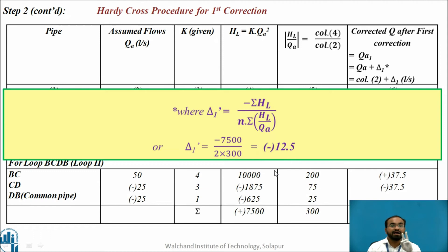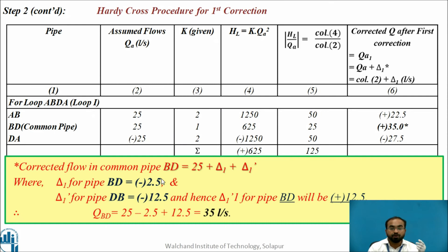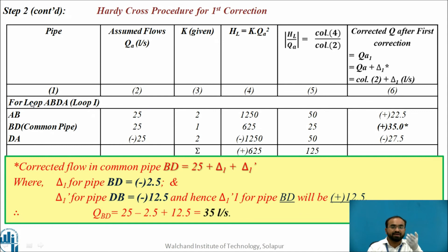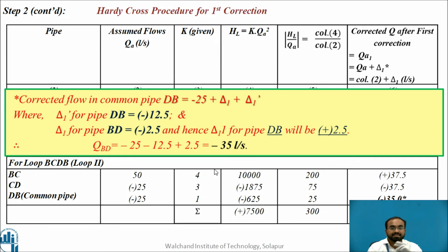For the common pipe B-D, two deltas apply — one from each loop. For BD in loop 1, the error is minus 2.5. For loop 2 it is DB with error minus 12.5; converting to BD direction gives plus 12.5. So the corrected flow for BD becomes 25 minus 2.5 plus 12.5, giving 35 liters per second. For loop 2, the same pipe appears as DB with opposite sign, giving minus 35 liters per second — this serves as a check. These are the corrected flow rates after iteration 1, summarized in a table and shown in the figure.